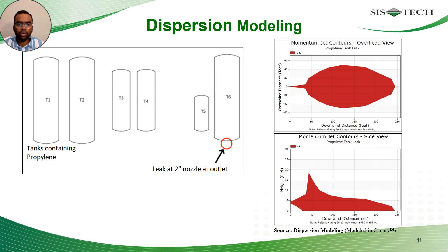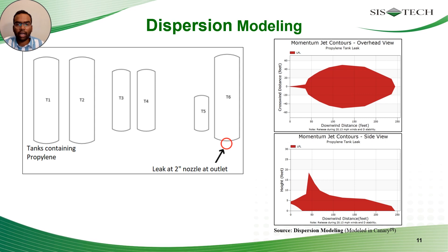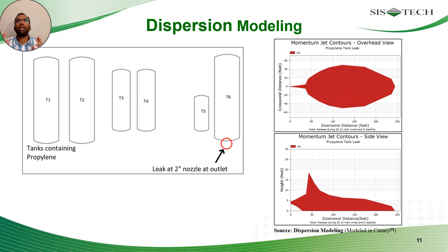Consider a situation where a chemical is leaking from a storage tank from a two-inch nozzle at 300 psi pressure and 88 degrees Fahrenheit temperature. You can use simple Gaussian models to get the release contours. In this case, it's a high-pressure scenario, so it is a momentum jet — you get the overhead view and the side view, which help you understand the footprint of the gas cloud in your facility. This becomes an input parameter for your scenario coverage calculations.